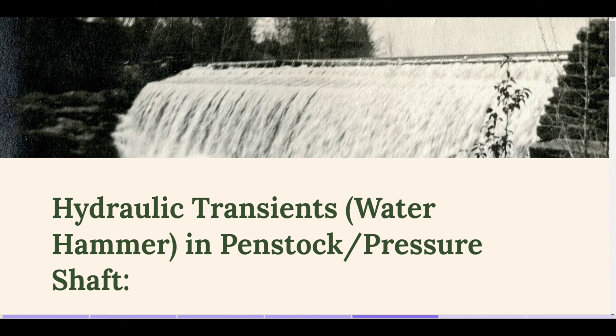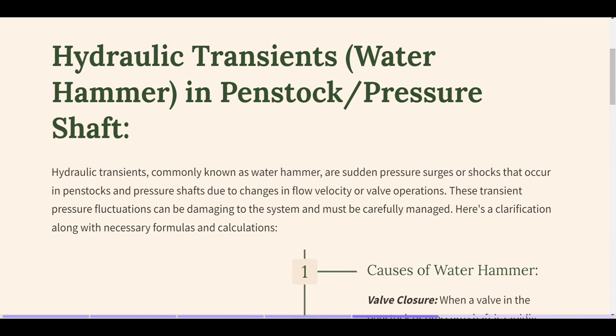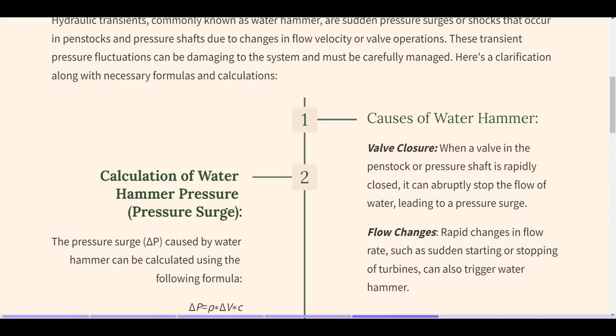Hydraulic transients, commonly known as water hammer, are sudden pressure surges or shocks that occur in penstocks and pressure shafts due to changes in flow velocity or valve operations. These pressure fluctuations can be damaging to the system and must be carefully managed. Causes of water hammer: valve closure — when a valve is rapidly closed, it can abruptly stop the flow of water, leading to a pressure surge. Flow changes — rapid changes in flow rate, such as sudden starting or stopping of turbines, can also trigger water hammer.